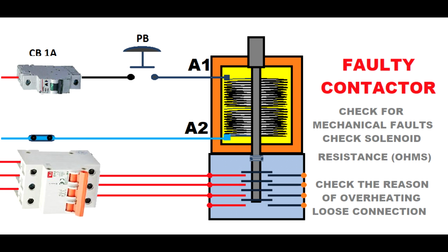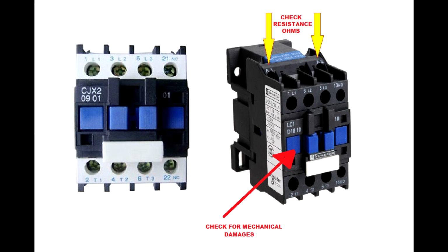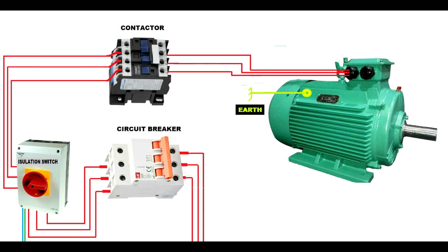Look, here's your contactor. You have a solenoid. If you check the resistance between A1 and A2, you might not have the right value. You also have to check for mechanical damage. You see this. In the real world, a contactor looks like this. You have to check the resistance between A1 and A2, and also check for mechanical damage, and then you have to investigate the reason why you had a mechanical damage, or maybe why your solenoid burned. Maybe you have a loose wire on a power circuit, and when you convert the electricity into heat, maybe you cooked the contactor. That would be a lack of maintenance.